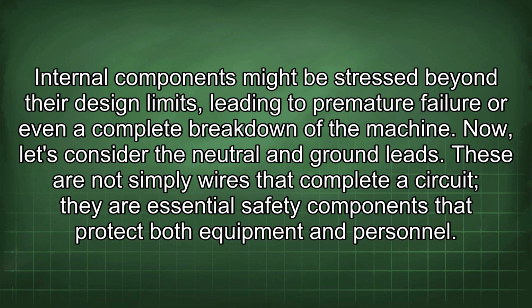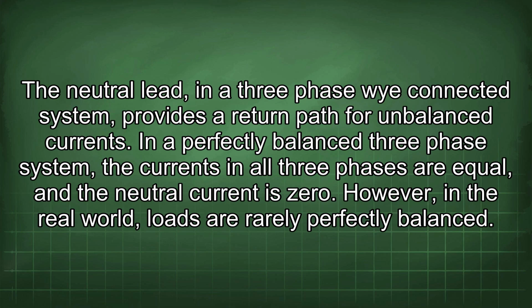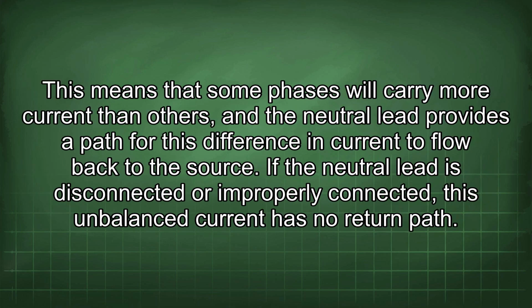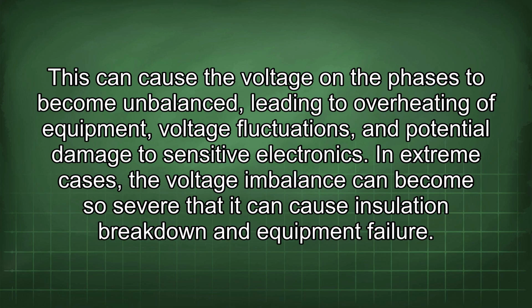Now let's consider the neutral and ground leads. These are not simply wires that complete a circuit, they are essential safety components that protect both equipment and personnel. The neutral lead in a three-phase Y-connected system provides a return path for unbalanced currents. In a perfectly balanced three-phase system, the currents in all three phases are equal, and the neutral current is zero. However, in the real world, loads are rarely perfectly balanced. This means that some phases will carry more current than others, and the neutral lead provides a path for this difference in current to flow back to the source. If the neutral lead is disconnected or improperly connected, this imbalanced current has no return path. This can cause the voltage on the phases to become unbalanced, leading to overheating of equipment, voltage fluctuations, and potential damage to sensitive electronics. In extreme cases, the voltage imbalance can become so severe that it can cause insulation breakdown and equipment failure.